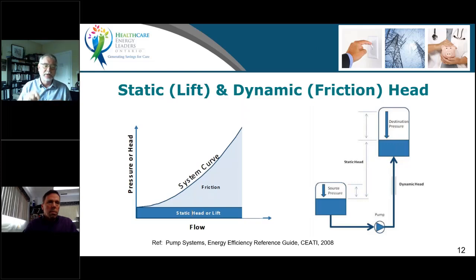And that has implications when it comes to applying speed control, which is where we're heading with all this in these types of systems. It will reduce the opportunity for speed control. Because we have a requirement for pressure, we have to maintain a certain amount of speed in order to overcome that pressure, in order to move water up that hill. It doesn't go to zero. So we can't. To that point, go ahead.